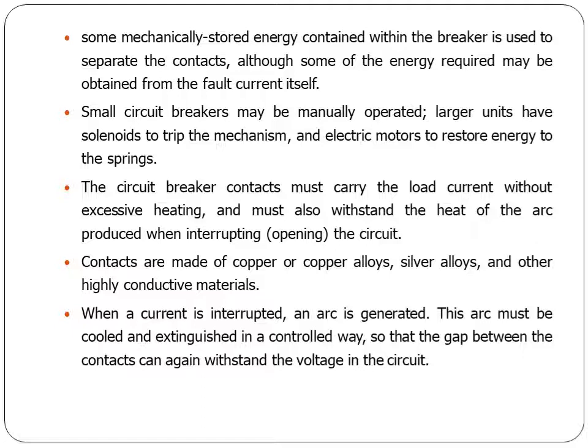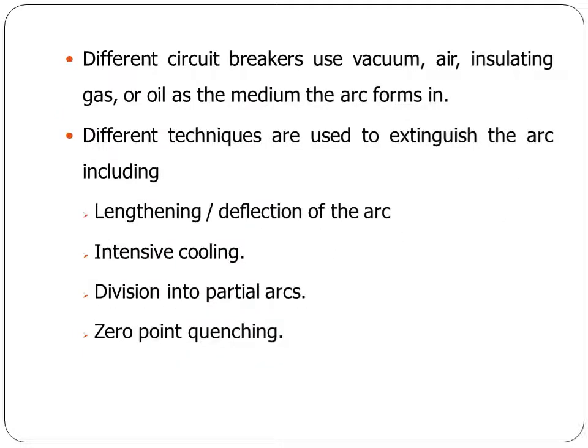Contacts are made of copper or copper alloys, silver alloys, and other highly conductive materials. When a current is interrupted, an arc is generated. This arc must be cooled and extinguished in a controlled way so that the gap between the contacts can again withstand the voltage in the circuit. Different circuit breakers use vacuum, air, insulating gas, or oil as the medium the arc forms in. Different techniques are also used to extinguish the arc, including lengthening, deflection of the arc, intensive cooling, division into partial arcs, and zero point quenching.